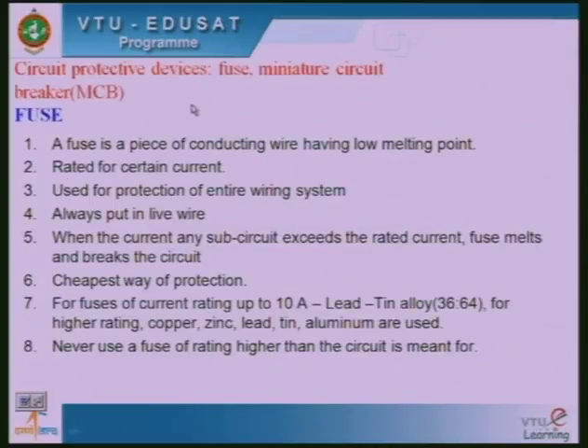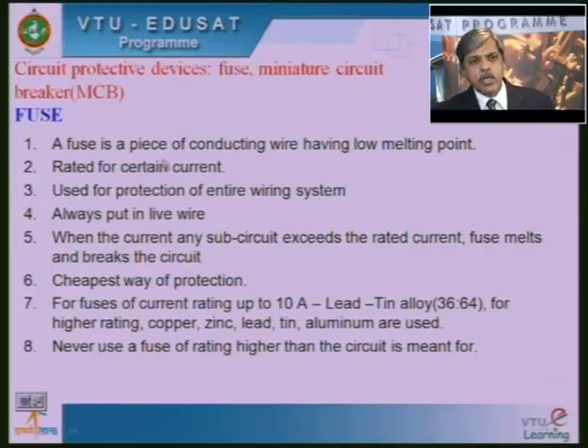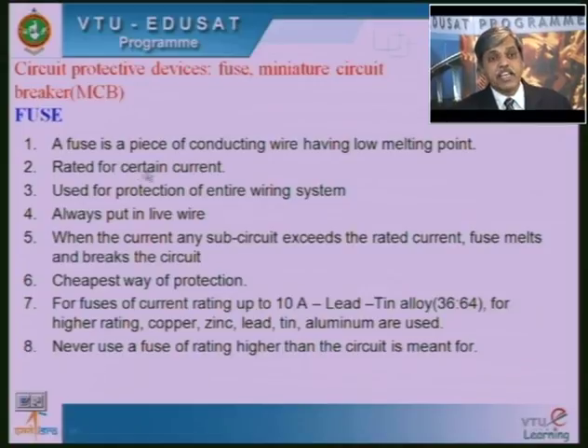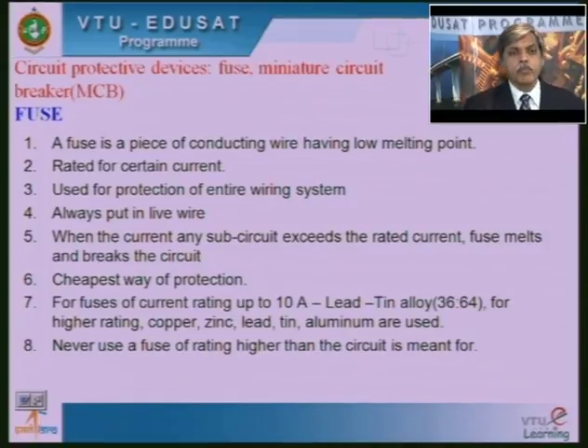Other circuit protecting devices, like the fuse and the miniature circuit breaker, we normally see in every household, MCB and fuse. There is a small difference. Both are protecting devices only, but the fuse is replaceable. It is a small piece of conducting wire having a low melting point. It should always have a low melting point so that protection to the circuit will be quicker. It is rated for a certain current. What is that certain current? It depends upon the current carrying capacity of our equipment.